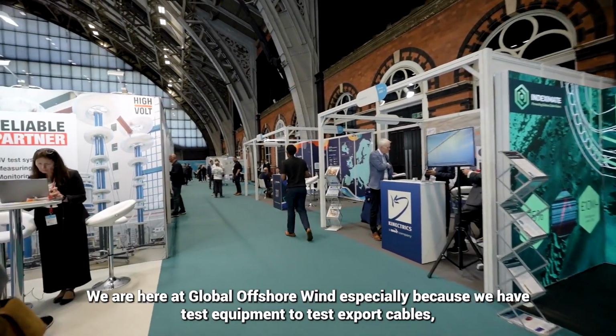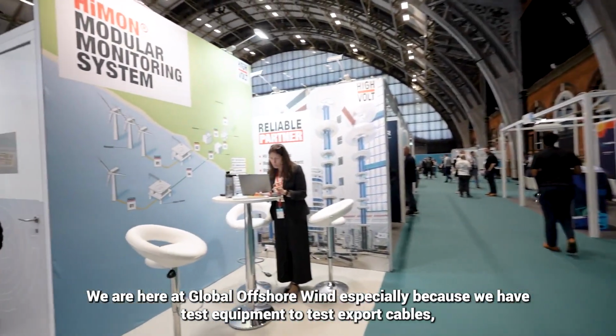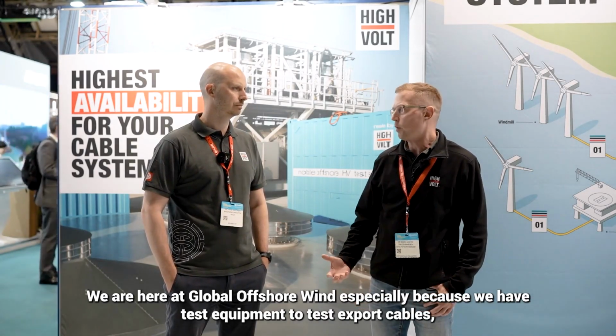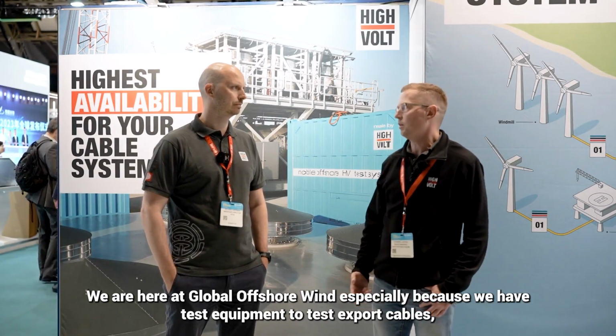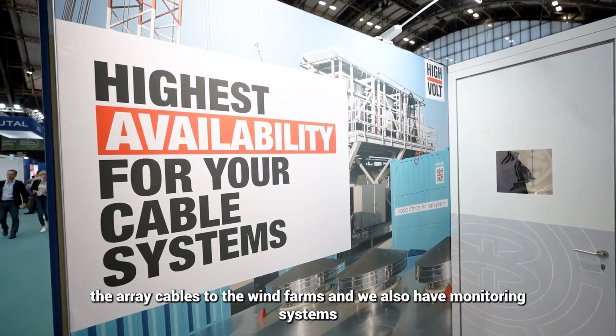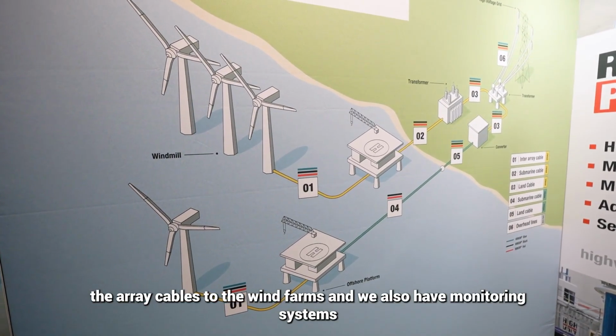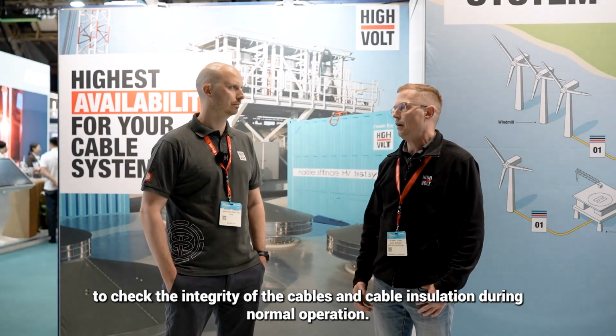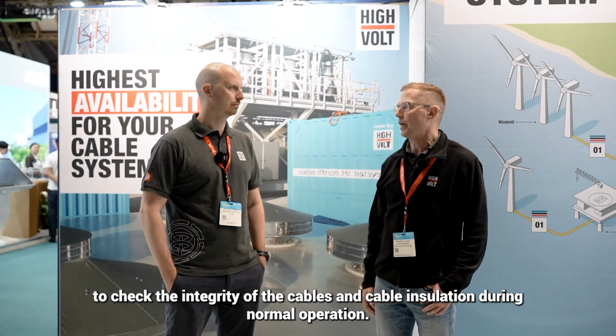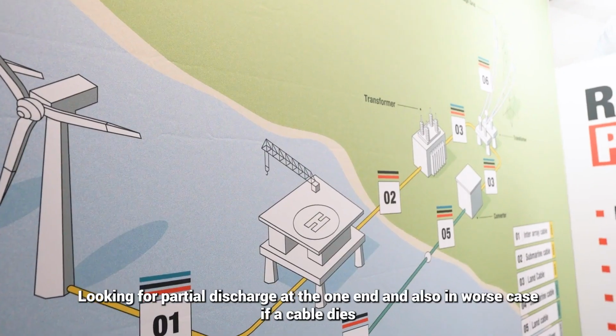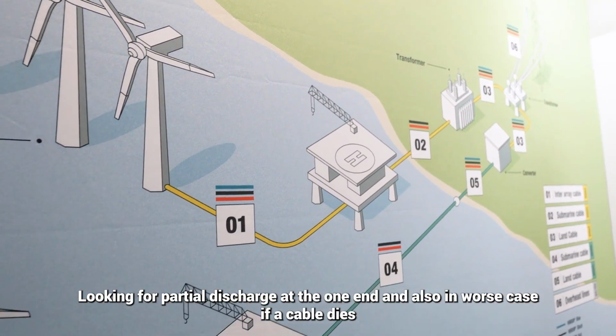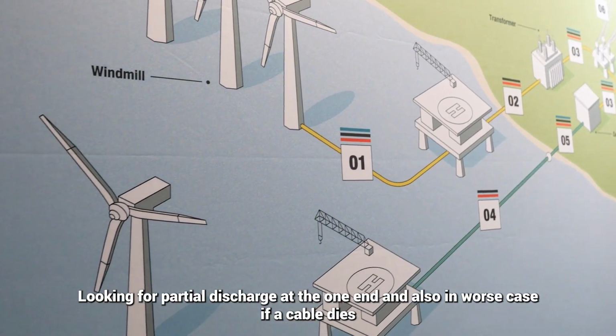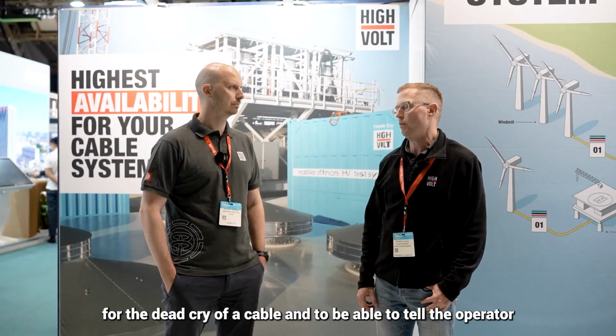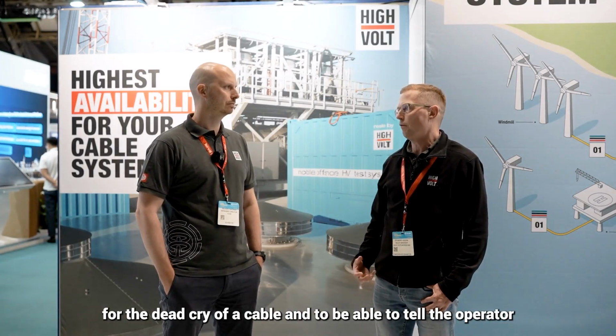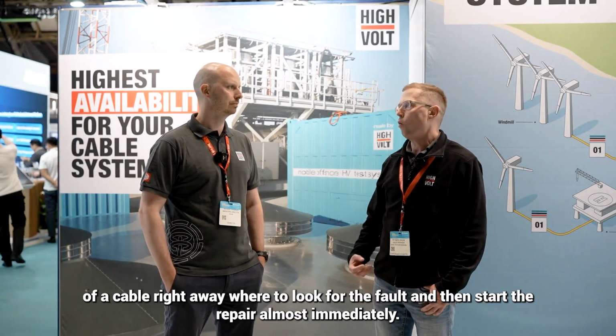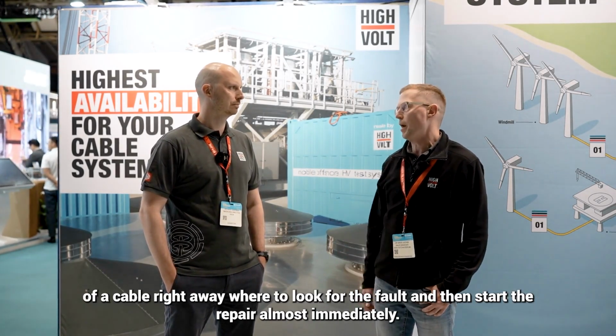We are here at Global Offshore Wind especially because we have test equipment to test export cables, the array cables to the wind farms, and we also have monitoring systems to check the integrity of the cable insulation during normal operation, looking for partial discharge on the one end, but also in worst case, if a cable dies, for the dead cry of a cable, and to then be able to tell the operators of the cable right away where to look for the fault and then start the repair almost immediately.